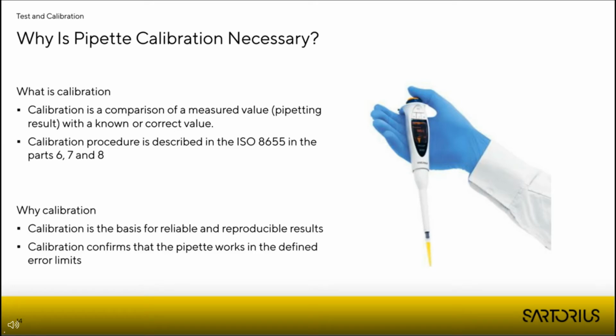During the calibration, a comparison of the selected volume, in our example the 300 microliter, with a known or correct volume is done. As a result of the calibration, you will see the systematic and random deviation of the pipette. In the new ISO 8655, there are now 3 different procedures described on how to perform such a pipette calibration. In part 6 and 8, reference measurement procedures are described, and in part 7, an alternative procedure is described.